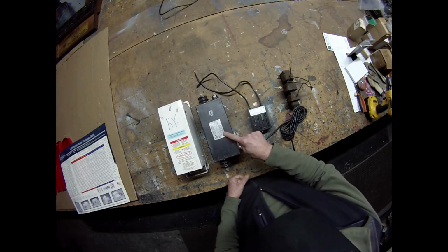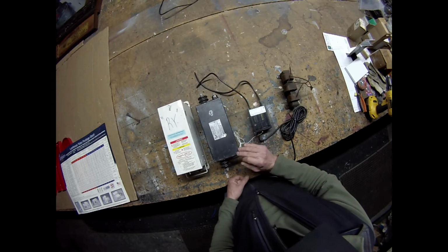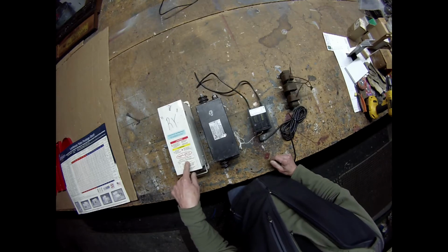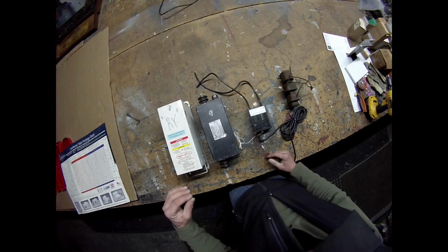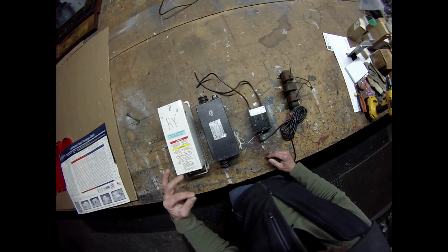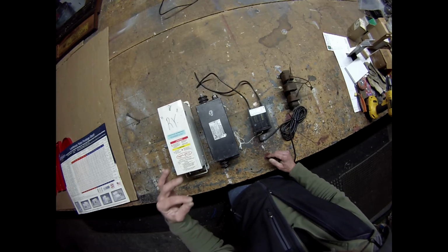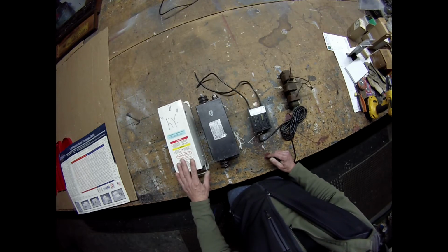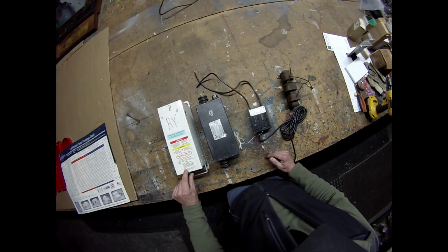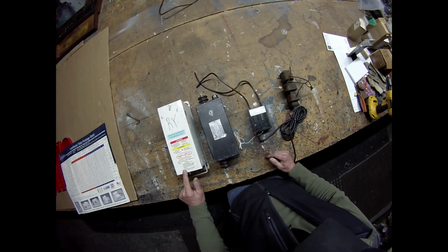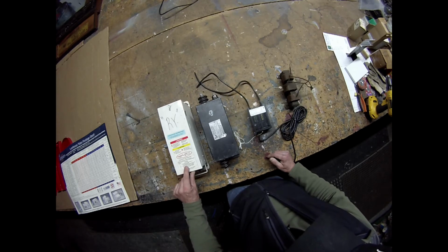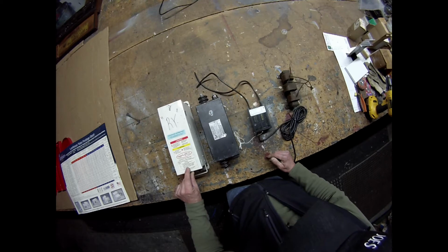This is a traditional transformer here that is not a smart transformer. This is a smart transformer. What this transformer does is it will react if there's any type of interference with the neon. If the neon is going bad, if there's a short, this transformer will automatically shut off. Then you can read the diagnostics here. It has a diagnostics chart, and there's a light on it, and the light will pulse. If it pulses once, it's a 15-second diagnostic in auto reset mode. If it pulses twice, a secondary ground fault exists. If it pulses 3 times, the unit is not grounded, or input, neutral, and line are reversed. If it pulses 4 times, the input voltage exceeds 120% of the rating.